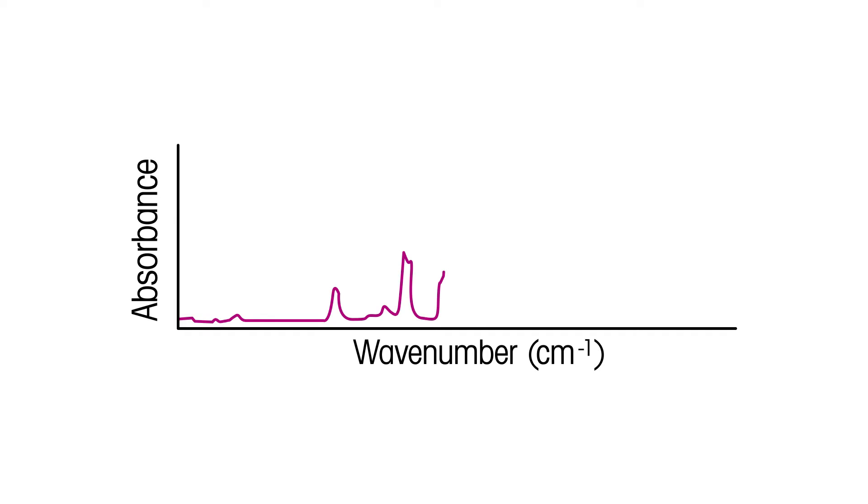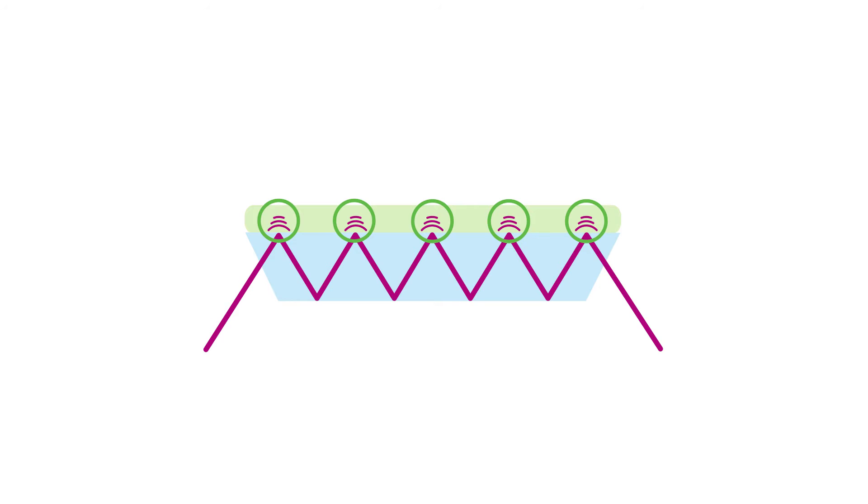As stated earlier, penetration depth is important because it is effectively your path length, and based on Beer's law, the larger the path length, the higher the absorbance is. In an ATR accessory, there are typically multiple bounces where the evanescent wave penetrates into the sample. In these cases, the real path length is the sum of each of these interactions, or bounces.